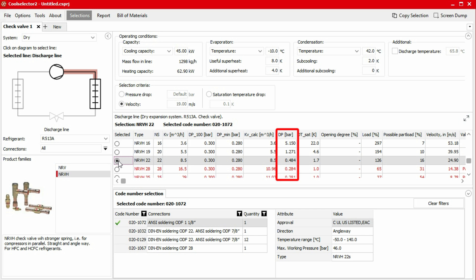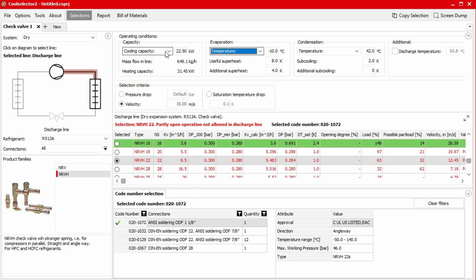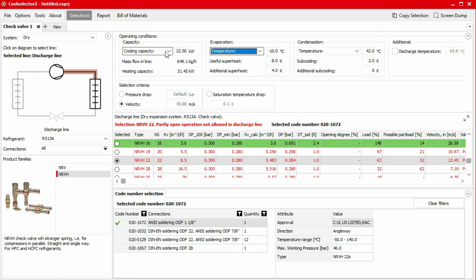You'll see in the table the pressure drop across the valve. You can also see that the load for this valve and system is 126%. This is the current load divided by the load required to fully open the valve. As we mentioned earlier, you should always make sure that the check valves are fully open in the discharge line. In our case, the system part load is 22.5 kilowatts. By replacing the capacity with this value, we can see that the suggested check valve is no longer applicable to our system as it is partially open. This shows the importance of considering the part load and other parameters to ensure that your selected product suits your system and requirements.